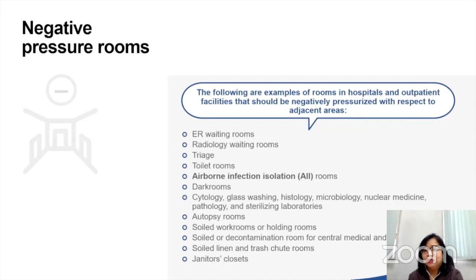For an airborne infection isolation room, it has to be negatively pressurized with respect to the other areas to prevent the contaminants inside that room from drifting to the other area. So it's keeping it in. But it doesn't just mean keeping it in the room, but rather there should be a controlled exhaust to take out this contaminated air without having to contaminate the rest of the areas.